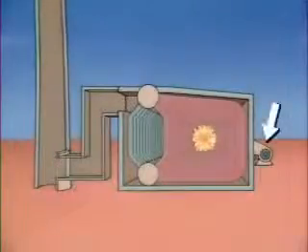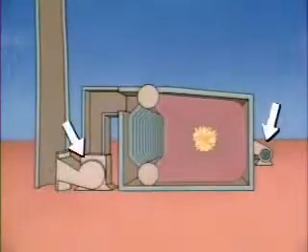Many boilers operate with only a forced draft fan; however, some boilers need both types to provide the proper draft. For example, in one configuration the forced draft fan supplies air to the burner and the induced draft fan draws out the hot combustion gas. The demand for steam from a boiler is called boiler load or steam load; when boiler load increases, more fuel must be burned to produce more steam.